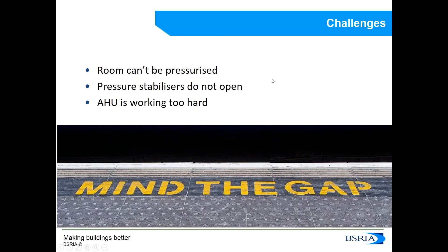When we build isolation rooms, we can face challenges. For example, rooms may not achieve the design pressure despite having correct supply and extract flow rates. It could be that the pressure stabilizer does not open, or that air handling units have to work harder than designed because the room is not getting enough pressurization. There can be a huge gap between the design of an isolation room and the real isolation room — most of these problems can be resolved with air tightness by finding and sealing the gaps.